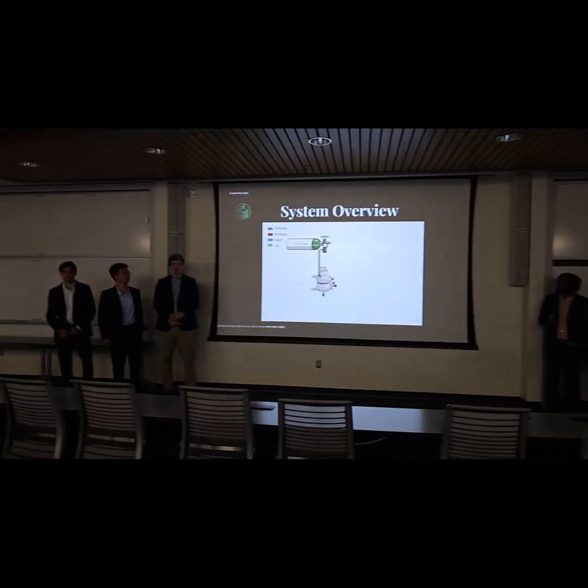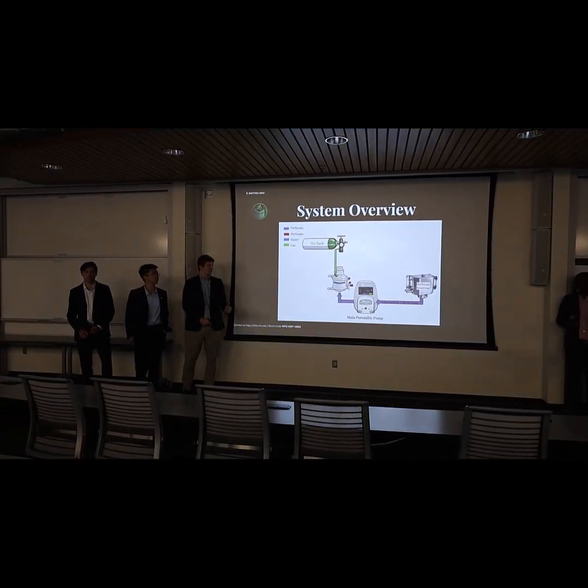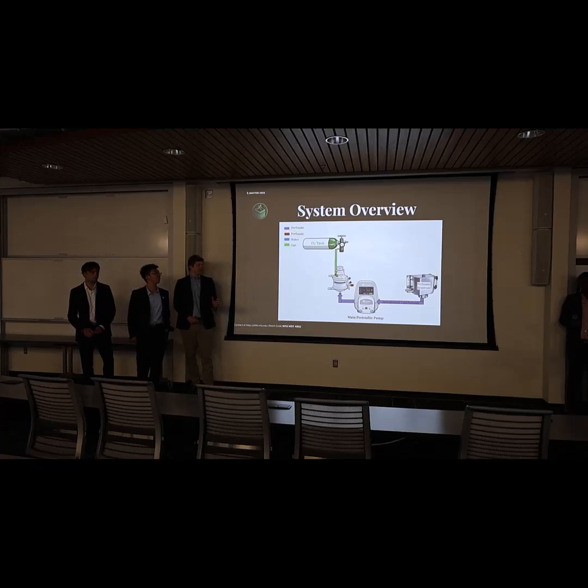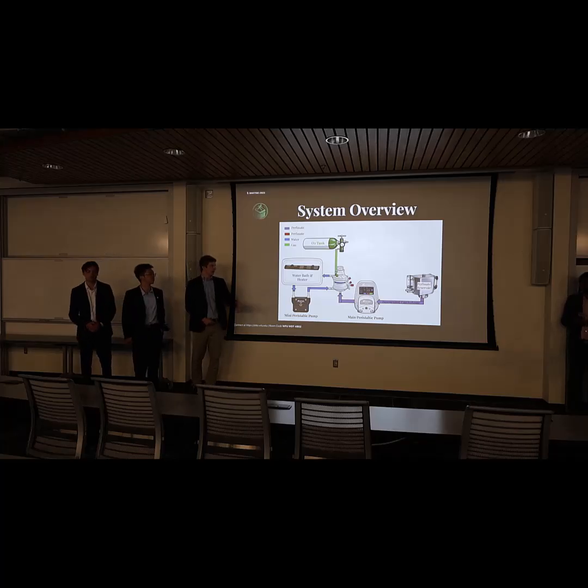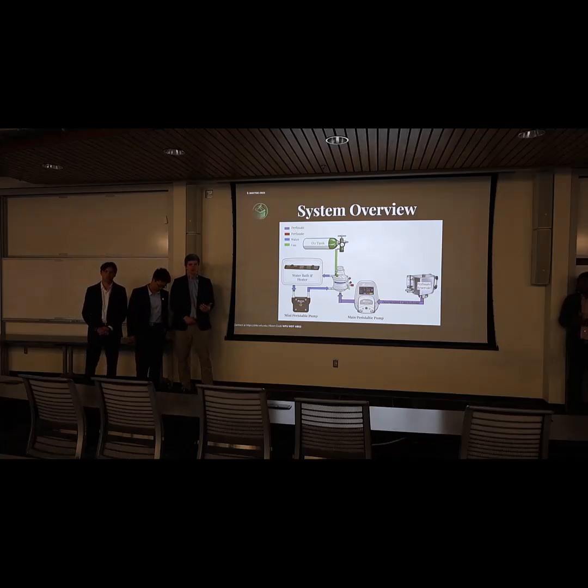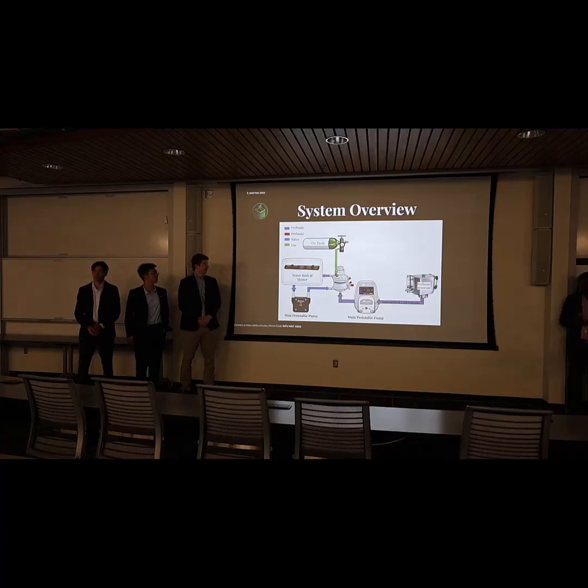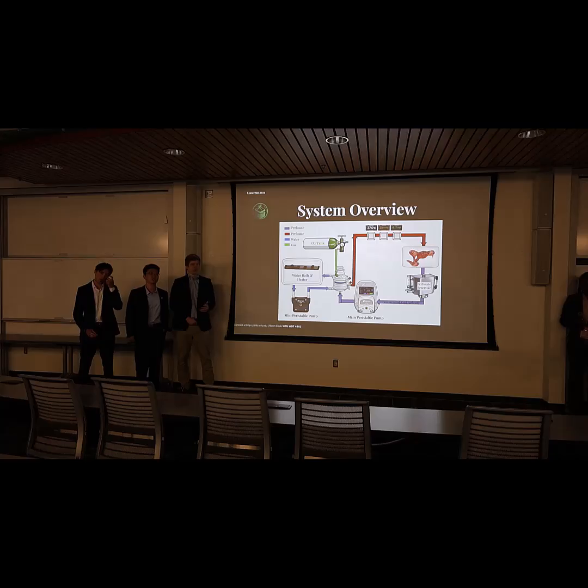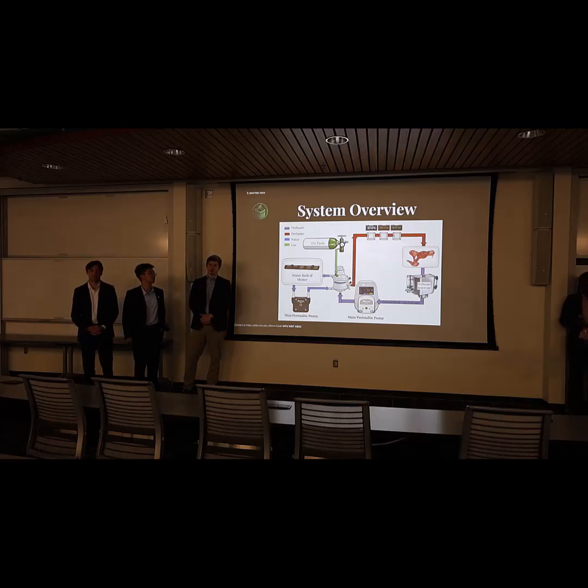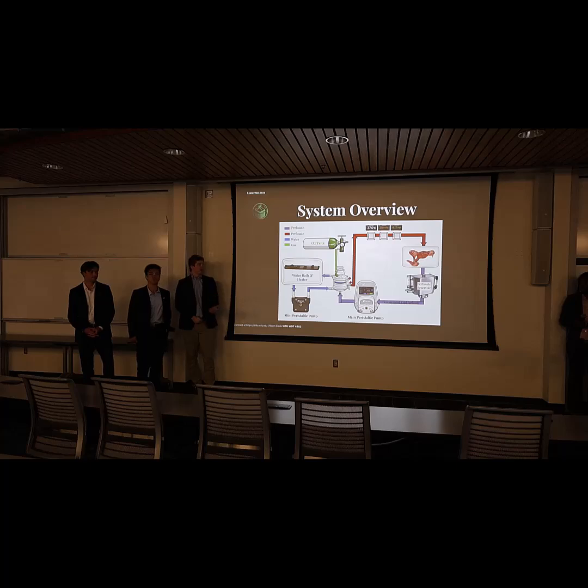Our system consists of 2 separate fluid loops. The first one starts in a perfusate reservoir where it is pumped into a central oxygenator. There it combines with the second fluid line, which consists of a heated water bath that continuously pumps heated water to heat the perfusate up to 37 degrees Celsius. The perfusate also undergoes oxygenation through the O2 tank before it makes its way to the pancreas. On its way to the pancreas, it passes sensors for temperature, pressure, and oxygenation, our system requirements, to ensure the pancreas is receiving optimal normothermic perfusion. After it perfuses through the pancreas, it returns back to the reservoir, completing the circuit.